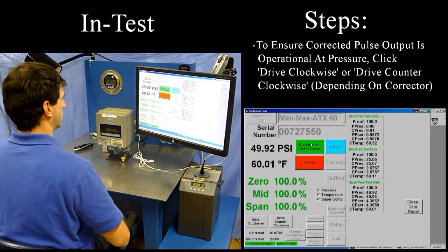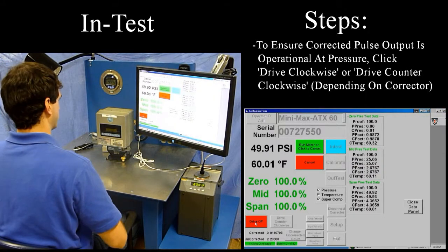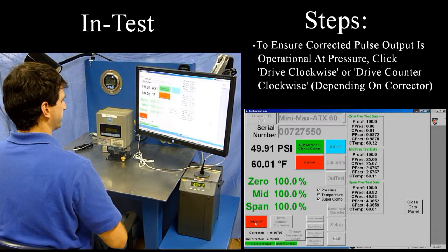After the span pressure test, the operator is prompted to run the drive motor either clockwise or counterclockwise depending on the corrector. This allows the operator to test the pulse output for both the corrected and uncorrected counts. If the operator wishes to change the uncorrected count to match the corrector's index, the Change Uncorrected Count button can be used to save the appropriate value to the corrector.